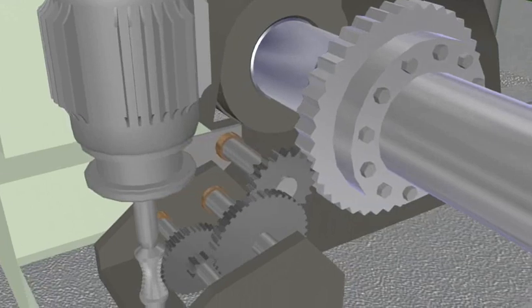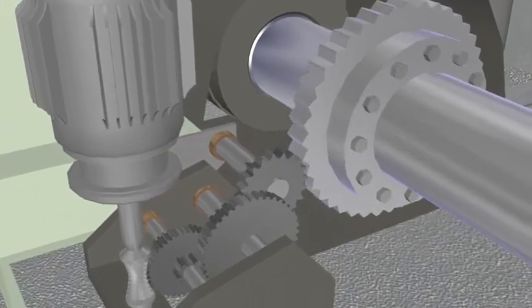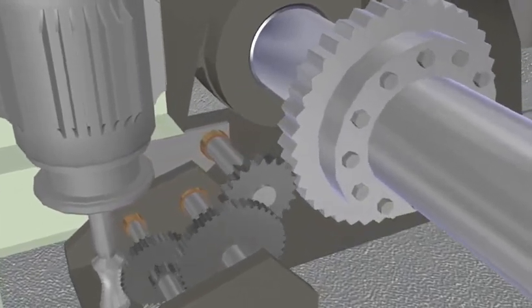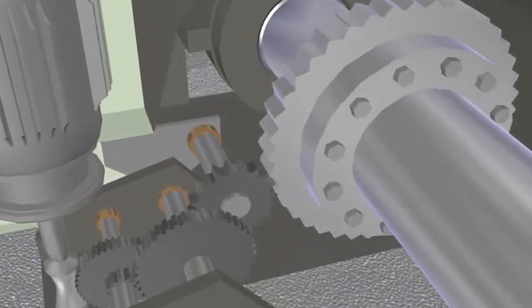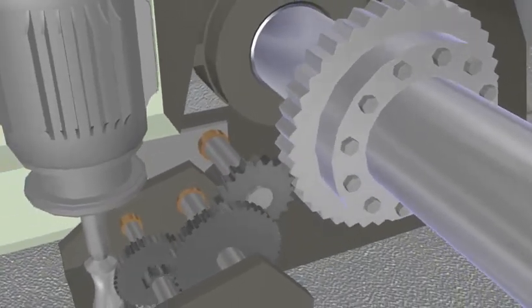The turning gear provides a slow rotation of approximately three revolutions per minute to correct rotor bowing or sagging due to uneven cooling or as a result of the rotor's own weight.